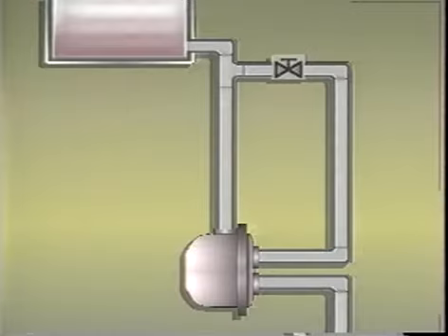To avoid differential shock arising from this situation, use an F&T trap and backvent it to the top of the vertical line to maintain near equal pressure throughout the riser, even if a slug of condensate forms.